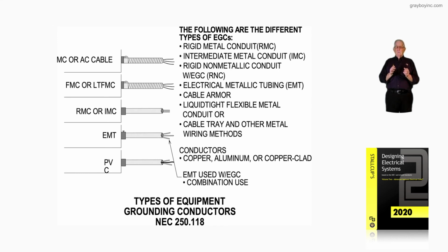So we go to 250.118 for this selection, but we go to 250.119 to determine the color coding or identification of insulation that might be on these equipment grounding conductors. And do not forget, always review 310.6 and 310.10 along with 250.118 and 250.119, and I think you'll get a good feel of this figure 16-108 when providing a grounding scheme.